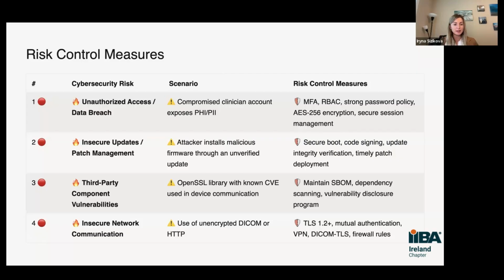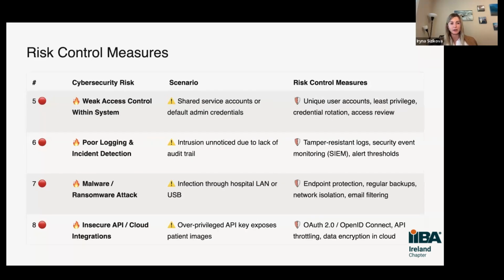So risk number 4 is insecure network communication. What could be a possible scenario? We use unencrypted DICOM, which contains a lot of personal patient information, or an insecure protocol like HTTP, for example, instead of HTTPS. How can we deal with that? As risk control measures, we can use TLS 1.2 and higher versions. Then authentication, we can use VPN while we are dealing with the software. We can apply firewall rules. Basically all of this reduces our risk for insecure network communications.